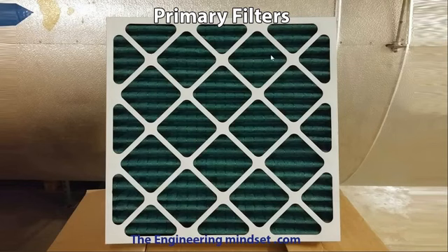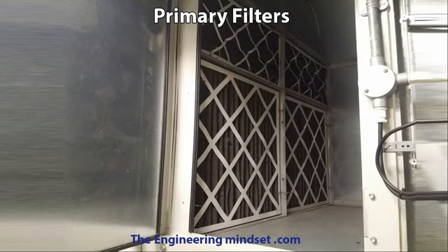Now the primary filters, which look like this, they are there to catch the dust. They're typically made in this pleated design, which increases the surface area and allows it to catch much more dust and last a bit longer than say if it were just a flat sheet. And they're usually made from a synthetic material with a cardboard outer frame, and they're held in shape with a wire mesh. And depending on the size of the AHU, you'll usually have to buy your filters in these pre-made sizes, and these will come and fit as filter banks within the AHU.